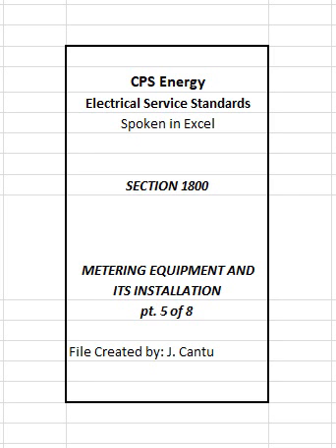Exception 2. Where 480-volt self-contained meter sockets are supplied from an auxiliary bus gutter, the maximum height may be increased to 6.5 feet to accommodate installation of meter disconnects. Exception 3. Where 4-stack and 5-stack modular metering is installed, the minimum height to the meter center of the lowest meter shall be 3 feet and the maximum height to the center of the highest meter shall be 6.5 feet. Note: enclosures for housing instrument transformers must be mounted so that their tops will be no less than 6 feet or more than 6.5 feet above final grade or floor level. Refer to Figure 1811.